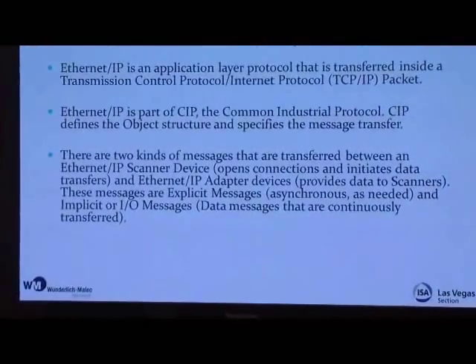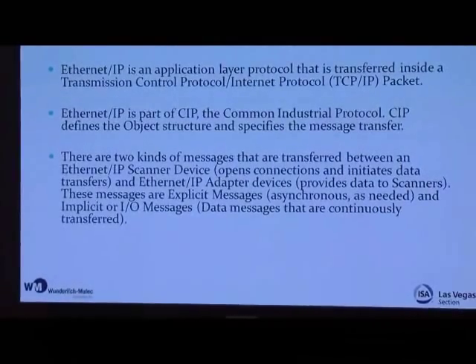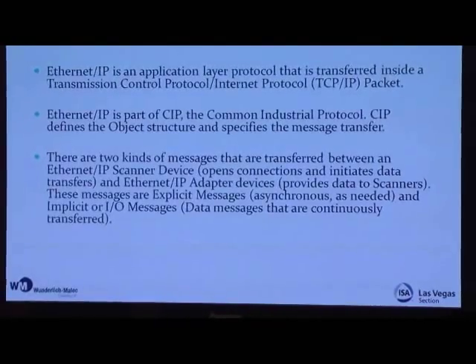When we talk about Ethernet IP devices, there are two kinds: scanners and adapters. Scanners are the devices you might consider the keeper or master — they initiate and control the communication. Adapters are slave devices or end nodes that provide data to the scanners. There are also two different types of messaging: explicit messaging, which is asynchronous, triggered either by a timer or an event; and implicit or IO messaging, which is a continuous connection where the scanner opens a permanent connection with the adapter and data transfer is continuous between the two devices.